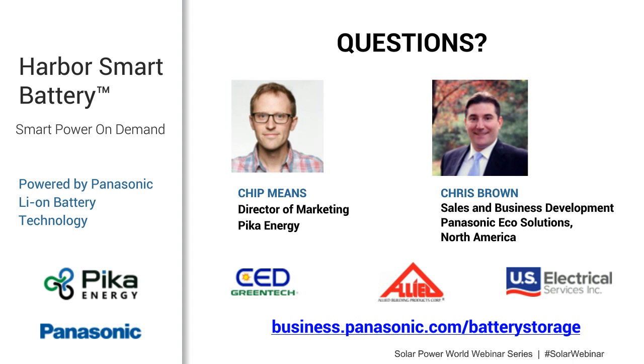Yeah, so if you had the 10P model, the power electronics device that's in both the 10P and the 15P is the same device, and it's Pika's B-Link battery converter, and it has a continuous output of 24 amps, so it goes right on one of those 30 amp breakers in the islanding inverter. So whether you have the 10 kilowatt hour Harbor battery or the 15 kilowatt hour Harbor battery, they both use the same amount of current from the power converter, and so they both go on a 30 amp DC breaker in the inverter, which means you could do up to 4 of either one.